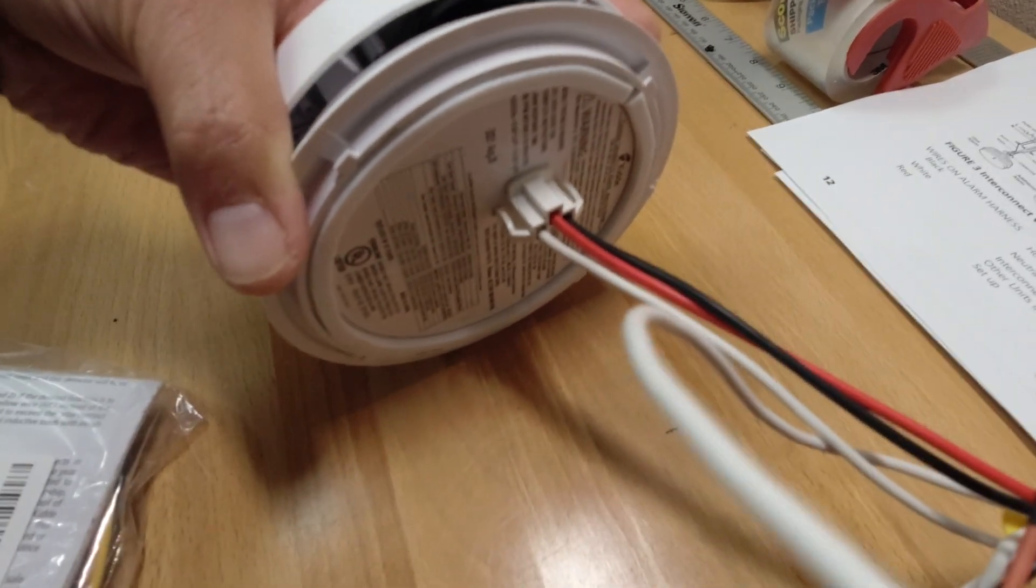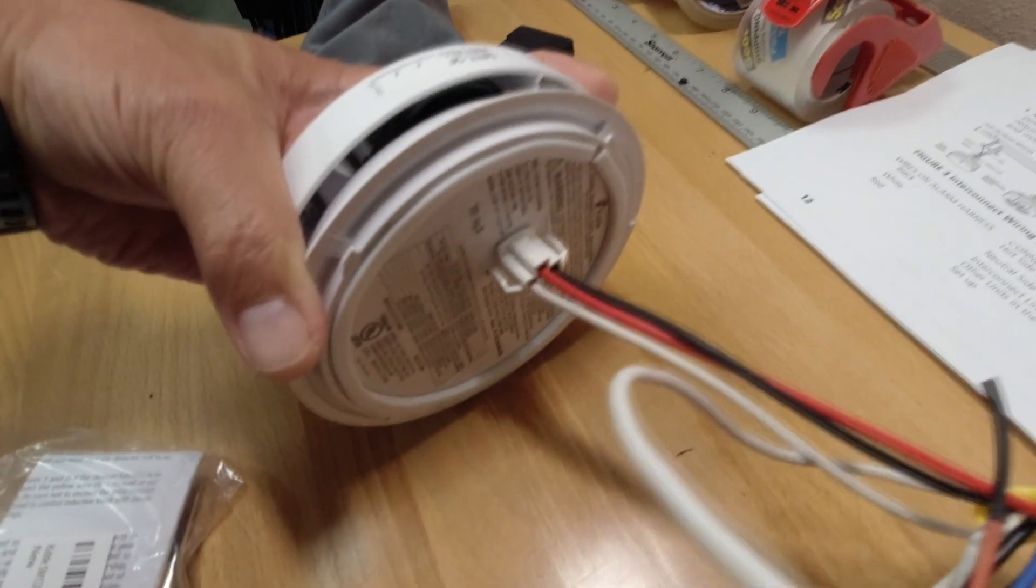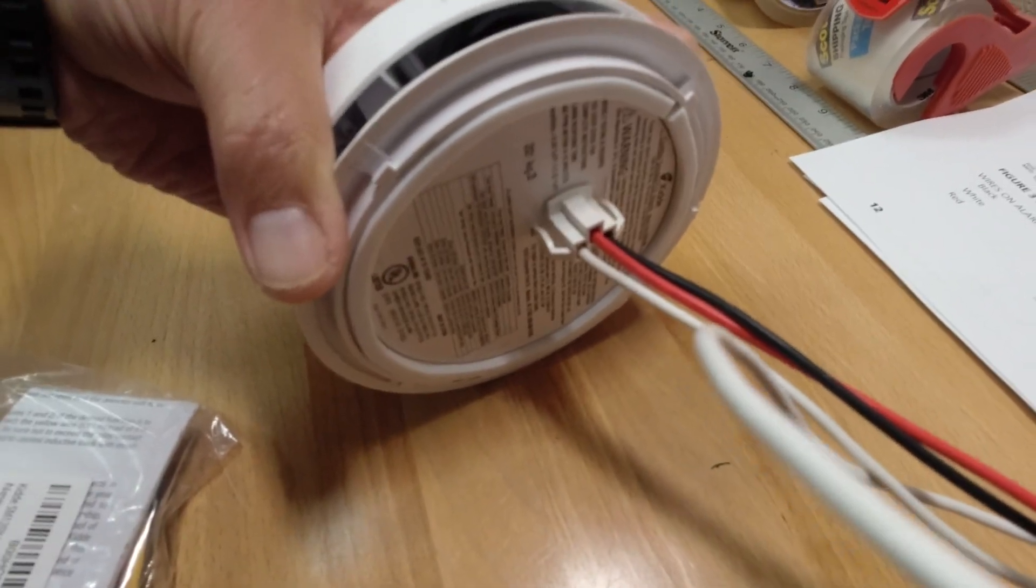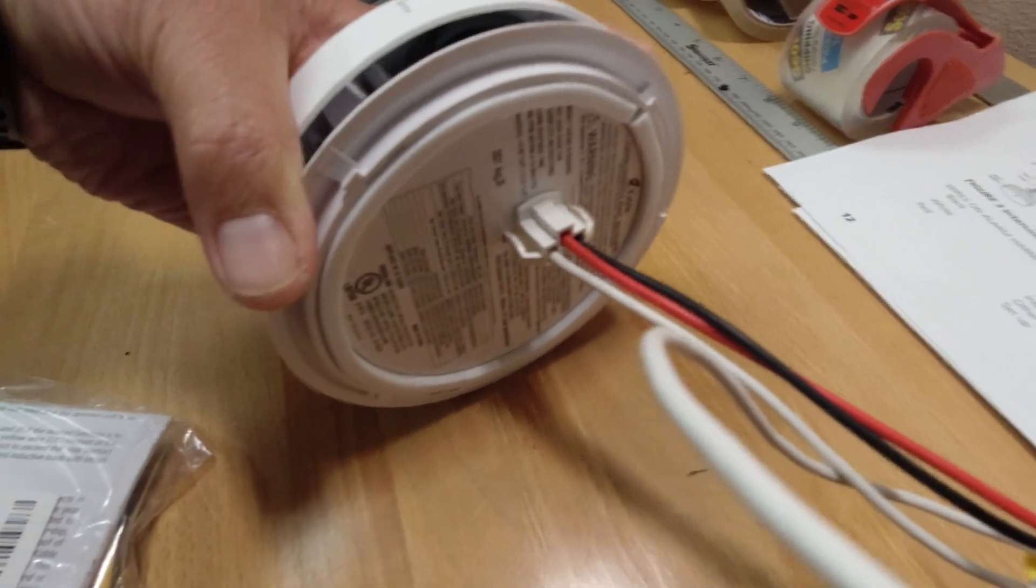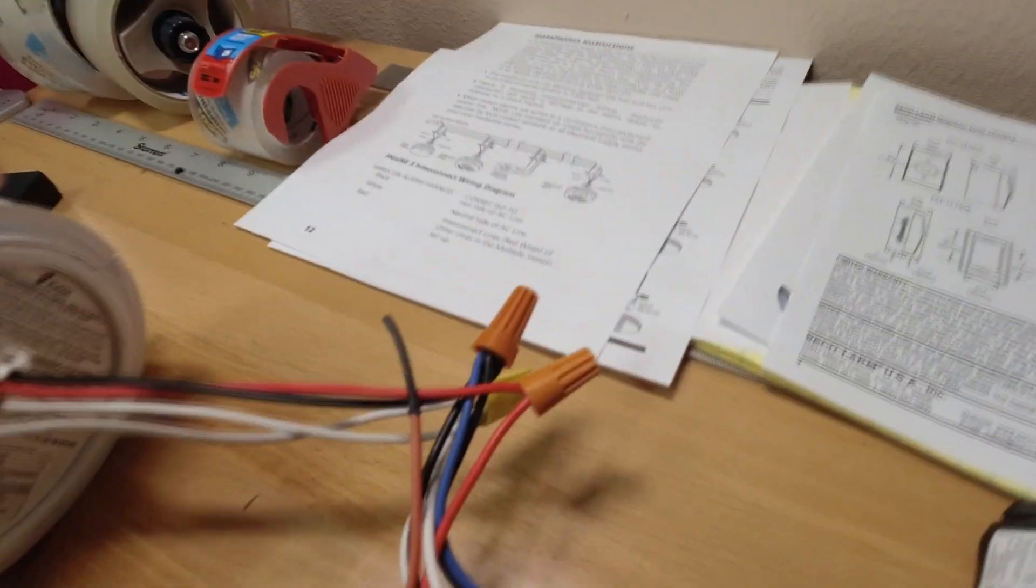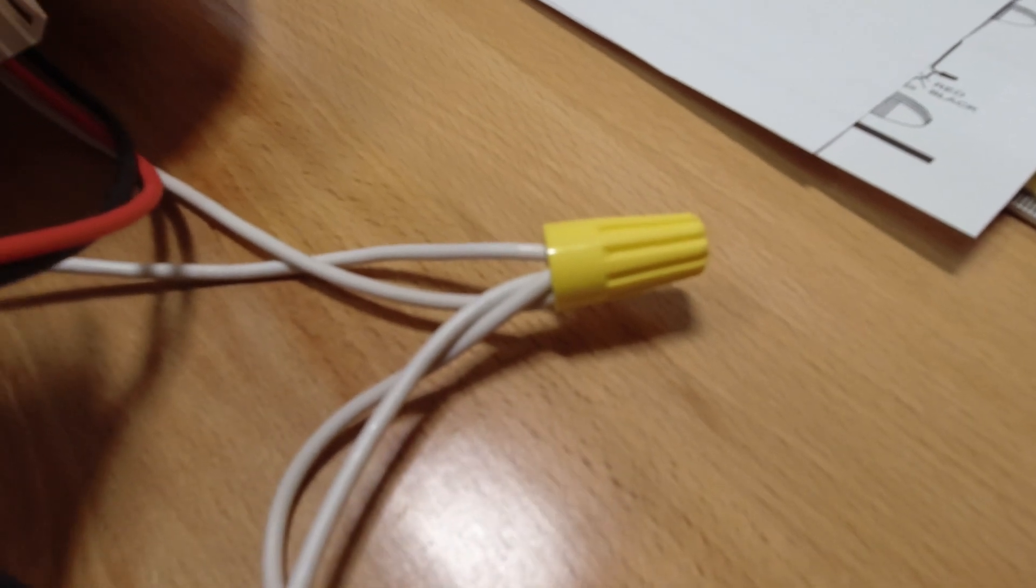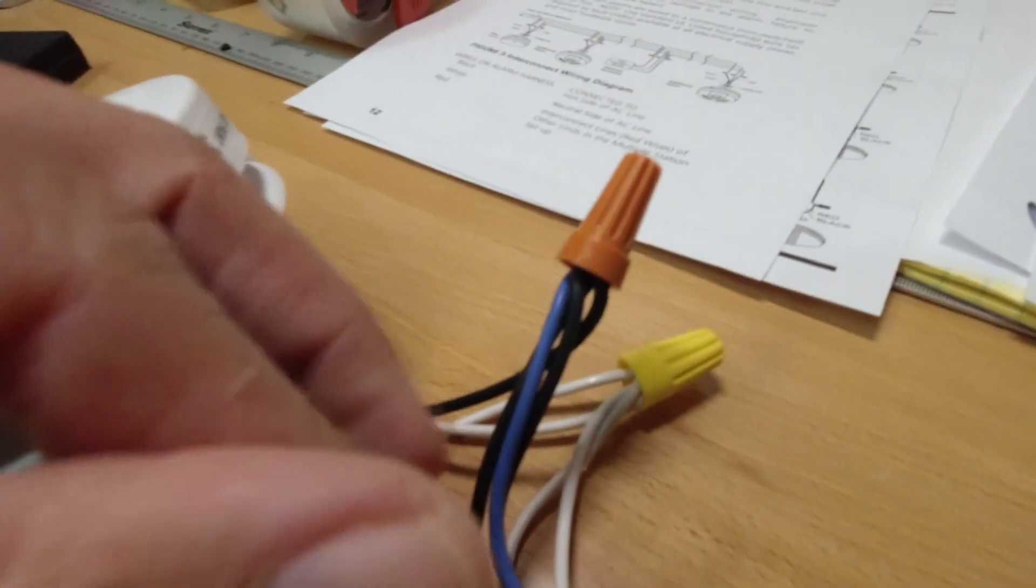So I got that and you have the black, red, and the white. The black is what I call black hot, as in 120 volts. The red is the signal that transmits the nine volt signal when it triggers, and the white line is the neutral wiring. As you can see here I have all the neutrals together and I have the blacks together. So the blue line is the common line that's going to the adapter.